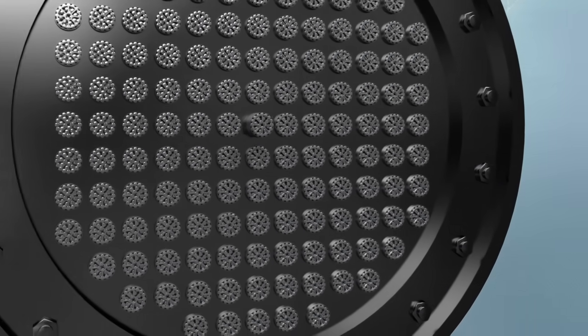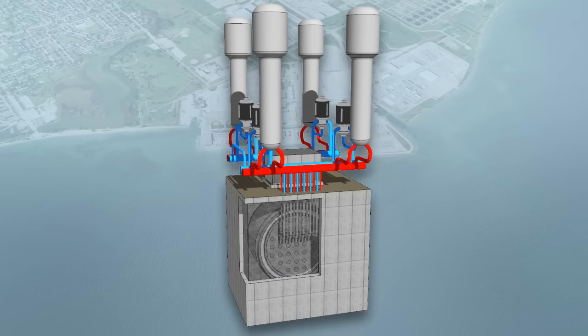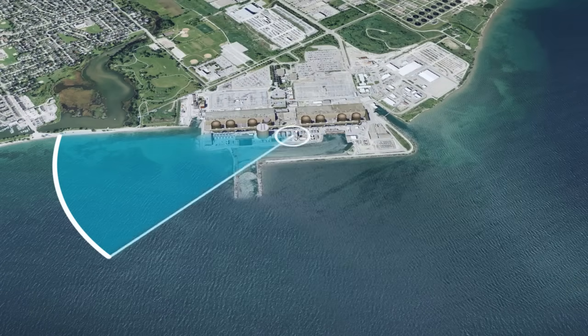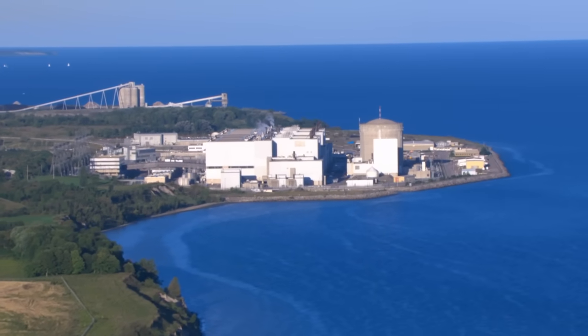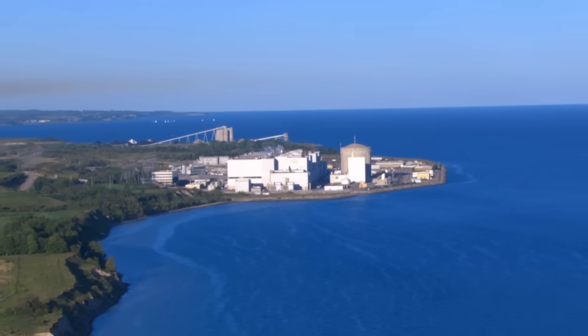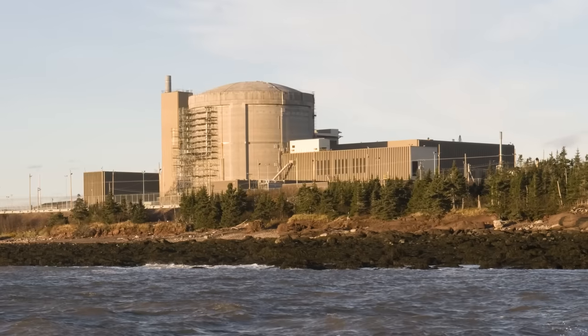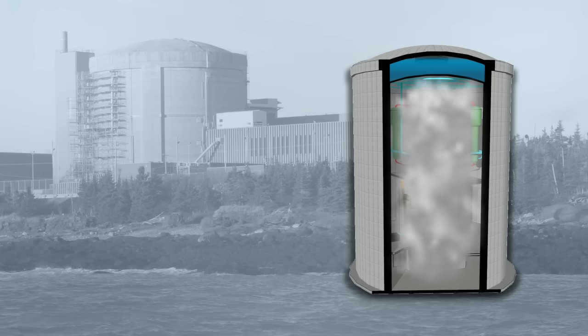The pressure tubes are contained inside a metal tank called the calandria, which itself is contained inside a thick vault made of reinforced concrete. The fourth layer of containment is the building that houses and protects the reactor — its walls are made of at least one meter of reinforced concrete, and the reactor building is surrounded by a one-kilometer exclusion or buffer zone. All plants are equipped with high-efficiency filters, used to minimize radioactive releases from nuclear power plants. These releases occur as part of normal activities like system maintenance. Filtering systems are regularly inspected, and power plant operators must, by law, report all radioactive releases into the environment.